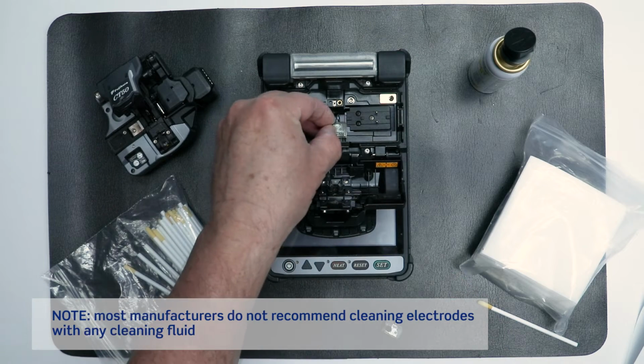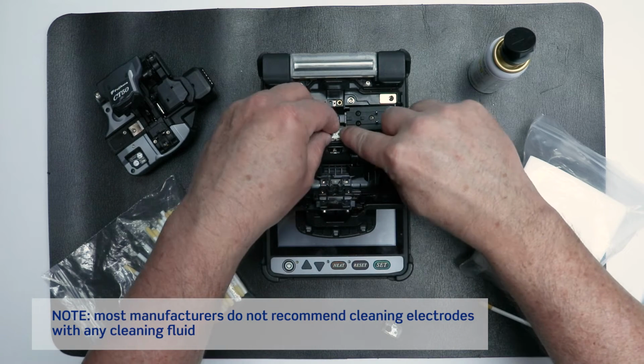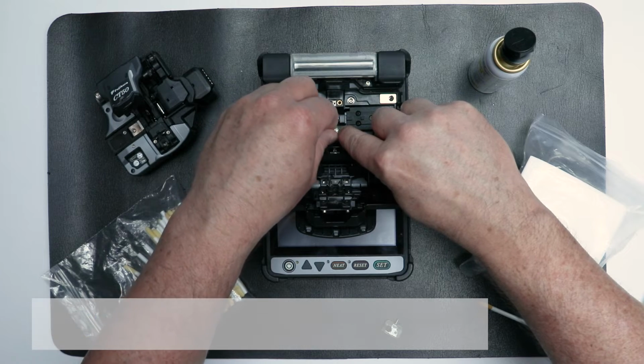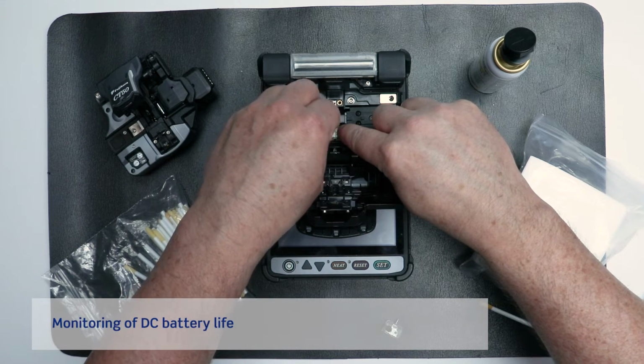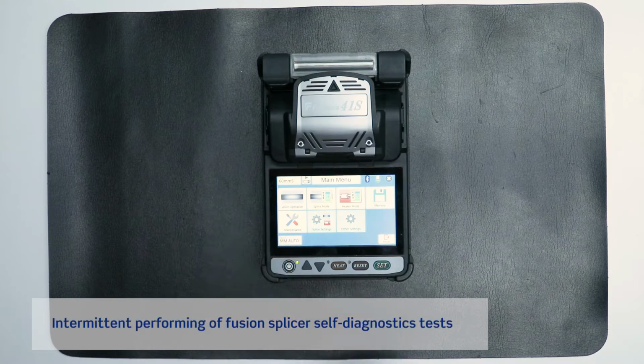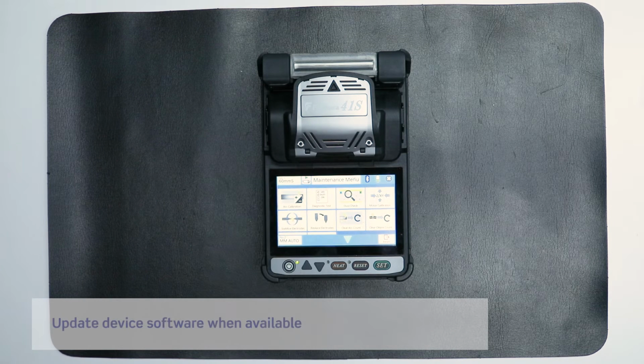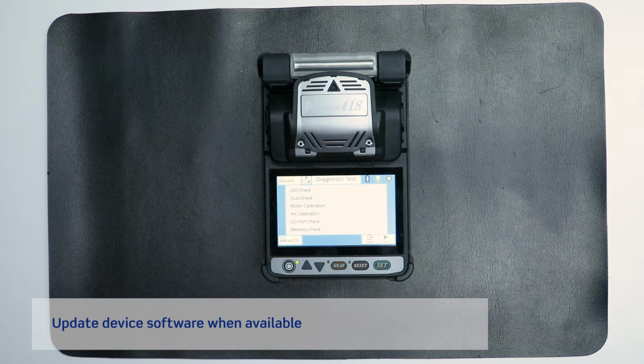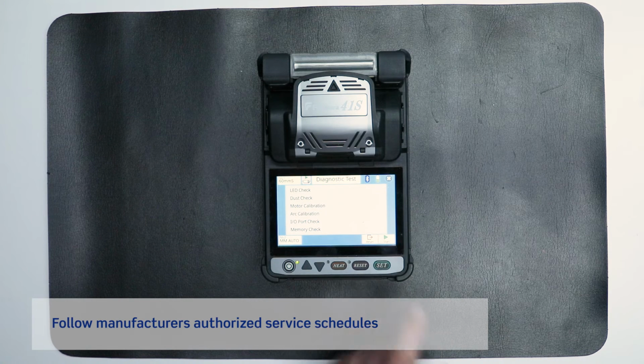Note, most manufacturers do not recommend cleaning electrodes with any cleaning fluid. Monitoring of DC battery life, intermittent performing of fusion splicer self-diagnostic tests, updating device software when available, and following the manufacturer's authorized service schedules.